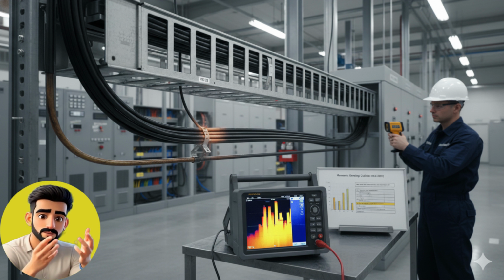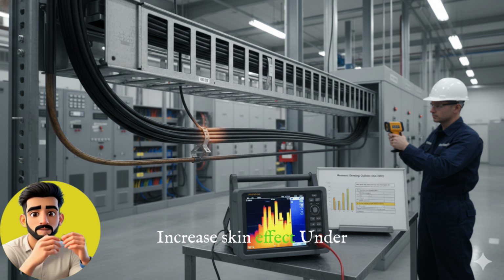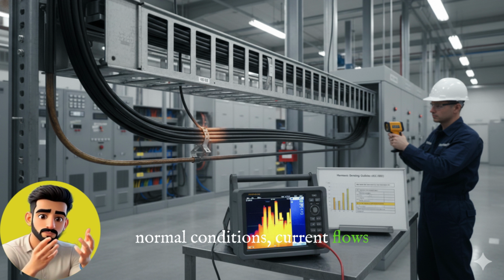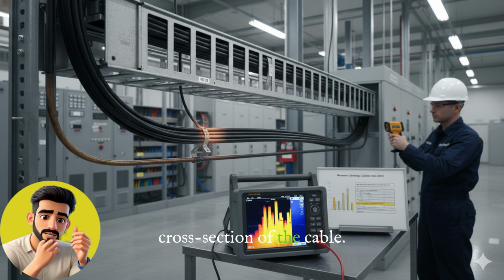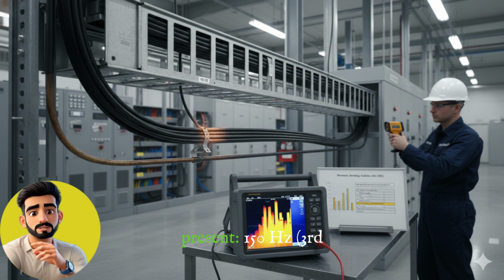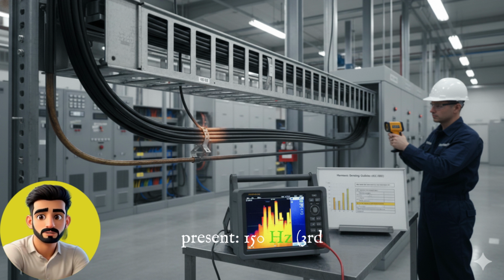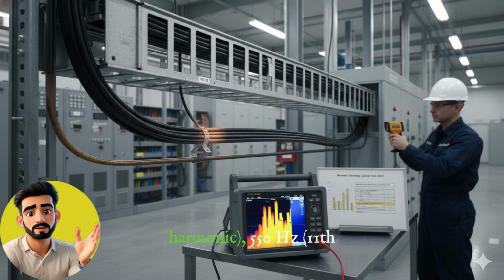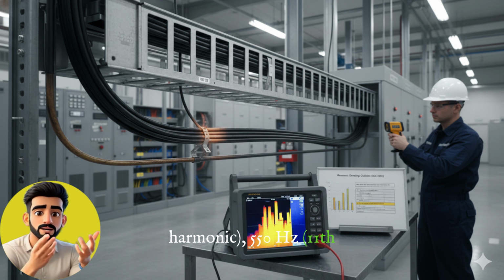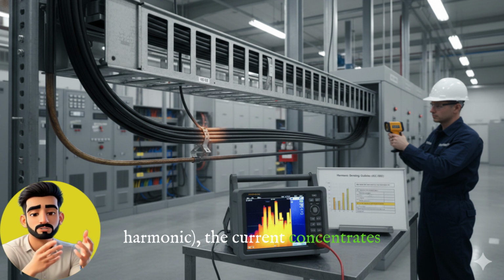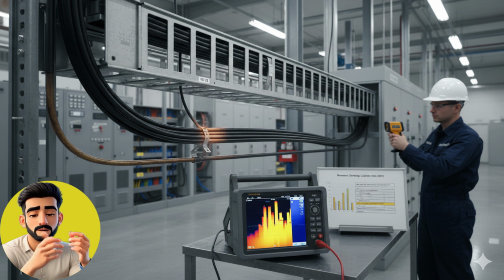High-frequency harmonics increase the skin effect. Under normal conditions, current flows through the entire copper cross-section of the cable. But when harmonics are present, 150 Hz, 3rd harmonic, 250 Hz, 5th harmonic, 350 Hz, 7th harmonic, 550 Hz, 11th harmonic, the current concentrates near the surface of the copper. This is called the skin effect.